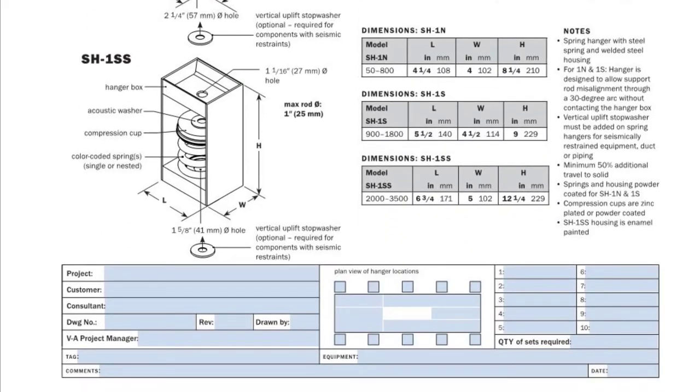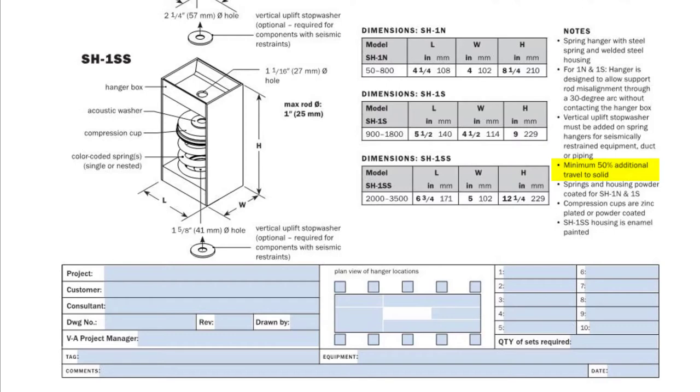Down in the notes section of the data sheet we see that the springs are all designed for 50% additional travel to solid which effectively means that the springs can support an additional 50% load until the spring coils all touch. So that SH-1S1100 isolator we just looked at can hold at least 1650 pounds before either spring goes solid and it no longer works as an isolator.